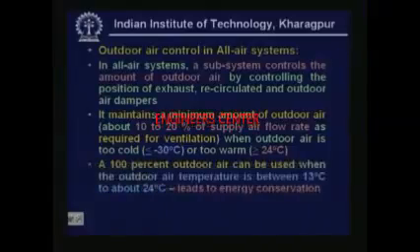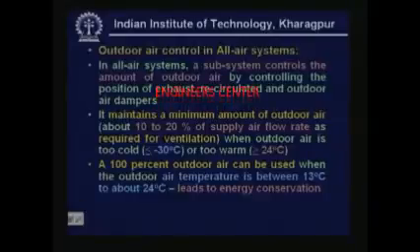However, the amount of outdoor air can be increased progressively as the outdoor air temperature increases from minus 30 degrees centigrade to about 13 degrees centigrade. And you can maintain 100 percent outdoor air when the outdoor air temperature is between 13 degrees and about 24 degrees centigrade. So when the temperature is less than minus 30 or greater than plus 24, you provide a minimum amount of outdoor air. When it is between minus 30 and plus 13, you progressively increase the outdoor air. When it is between 13 and 24 degrees centigrade, you supply all outdoor air for conditioning the space.